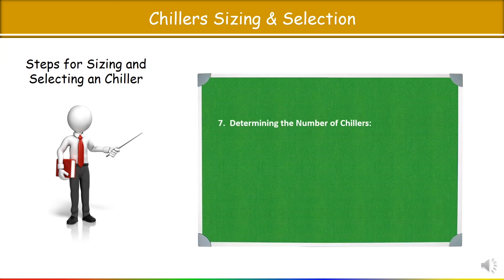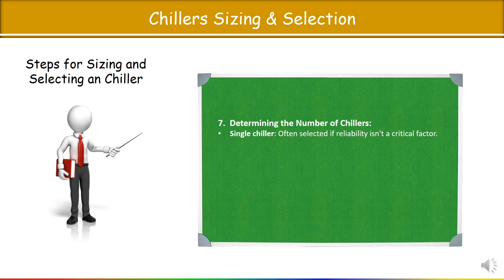The next step is to determine the number of chillers. A single chiller is often selected if reliability is not a critical factor. For a small cooling load, typically less than 100 tons, a single chiller is preferred — for example, small commercial buildings, retail spaces, or residential applications. A single chiller has lower initial capital cost and requires less physical space than multiple units.